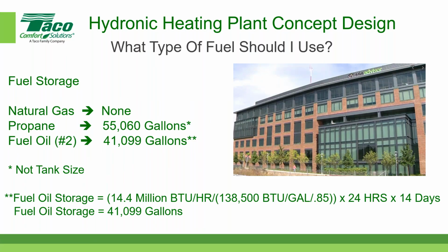Typical. So here you can see the fuel oil storage. If we have 14.4 million BTUs per hour, and approximately 138,500 BTUs per gallon, divided by the efficiency of 85%. The efficiency, by the way, could be much higher, especially if you're using condensing boilers. You'll see that some of the numbers I have here give you an option of using a conventional boiler or a condensing boiler. This would be at 100% capacity for our make-believe building. If we wanted storage for 24 hours times 14 days, it's 2 weeks' worth of storage, you would need approximately 41,000 gallons. So hopefully that makes sense to the folks in our audience today. And if they need more input, I'll be happy to provide some additional information.